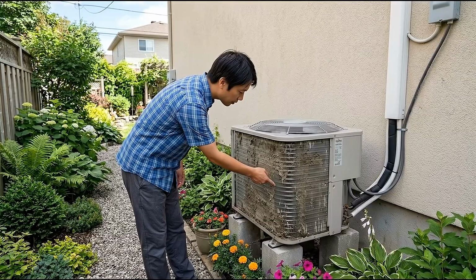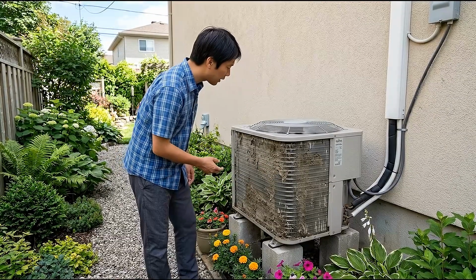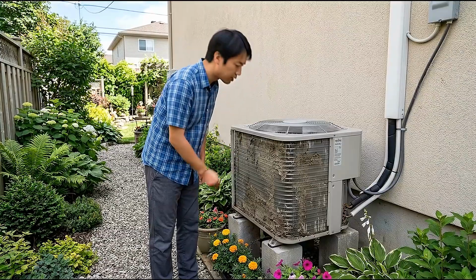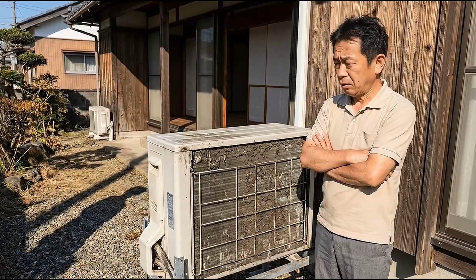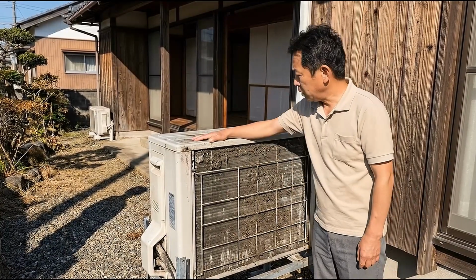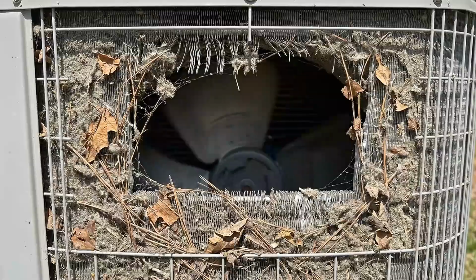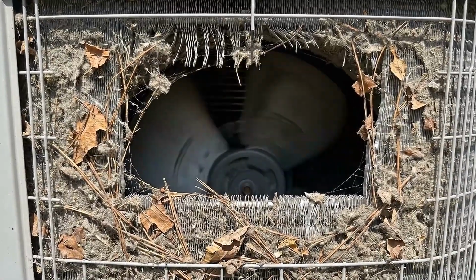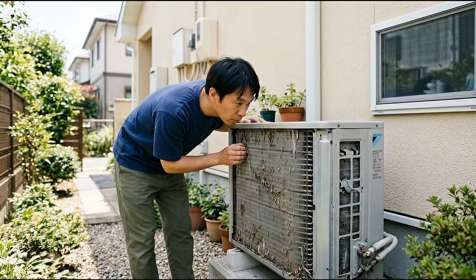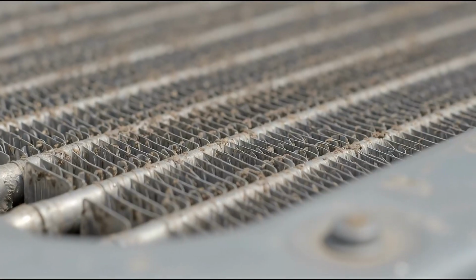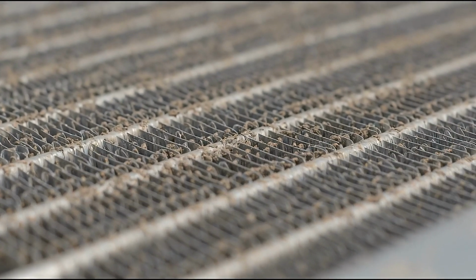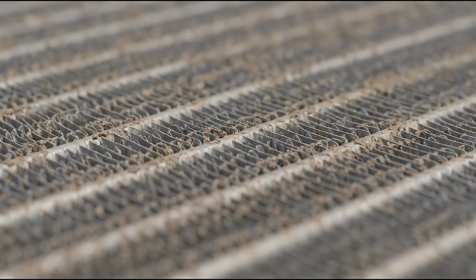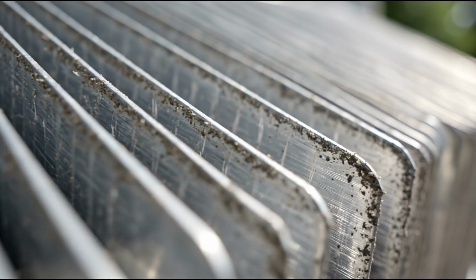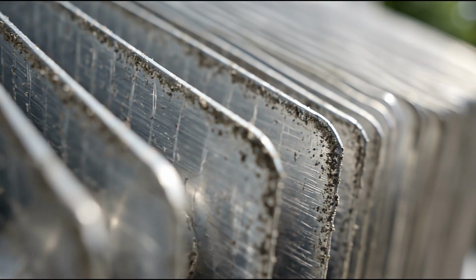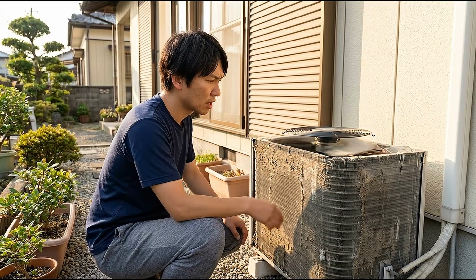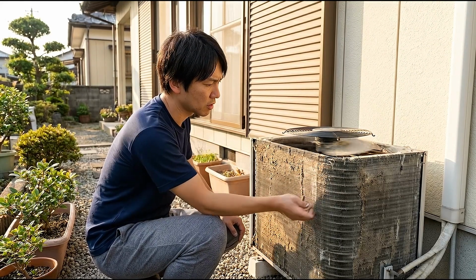The Department of Energy reports that dirty condenser coils can increase your system's energy consumption by up to 30%. That is nearly a third of your cooling electricity going to waste because the outdoor unit cannot breathe. And here is the part that matters for your wallet specifically. The EPA study found that a dirt layer, just 0.042 inches thick, thinner than the edge of a credit card, causes a 21% drop in efficiency and can increase refrigeration energy use by 35%.